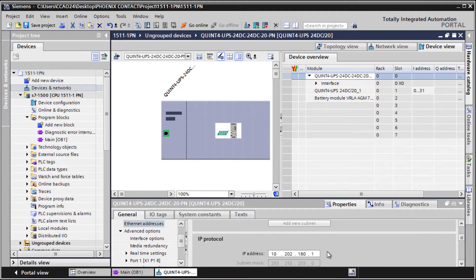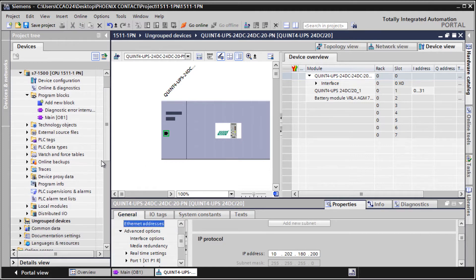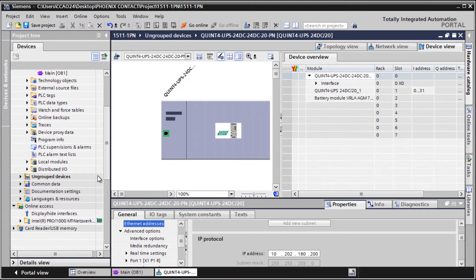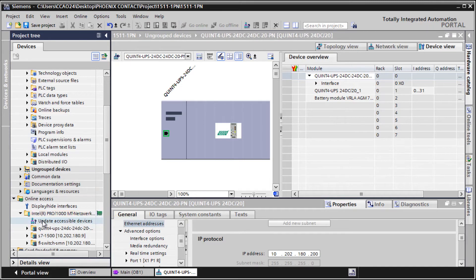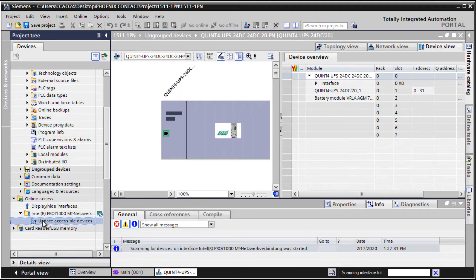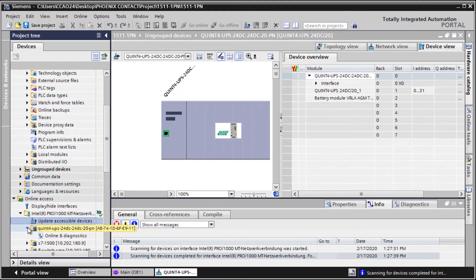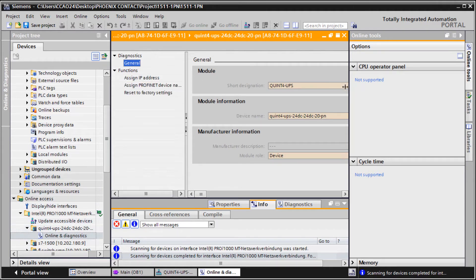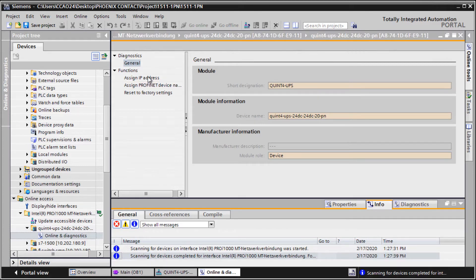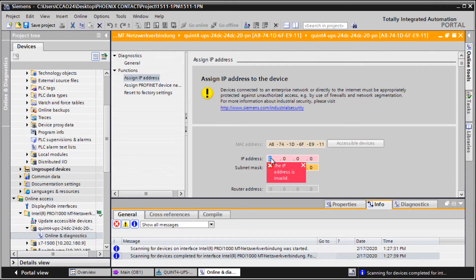Set an IP address for the UPS. Scan your network for available devices and then open Online and Diagnostics of your UPS. Enter the previously set IP address in the related fields and send it to the UPS.